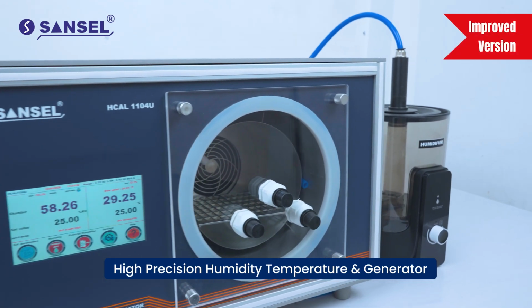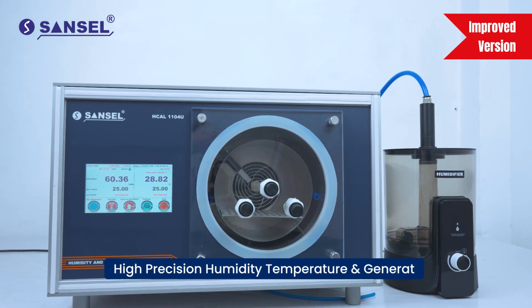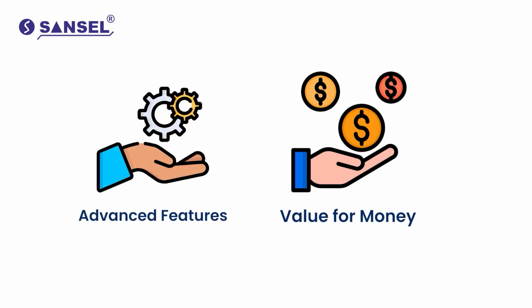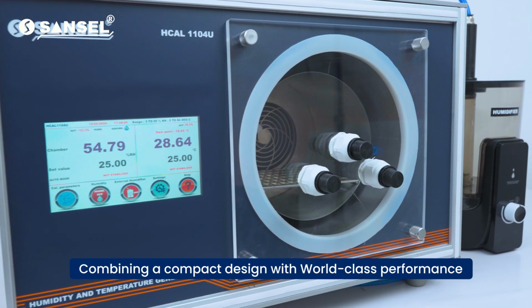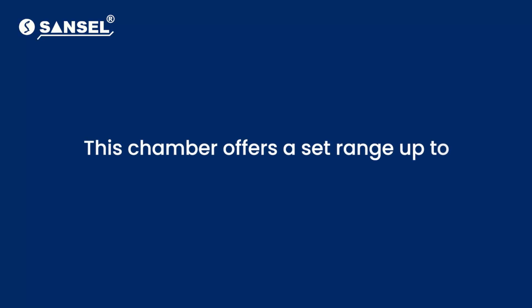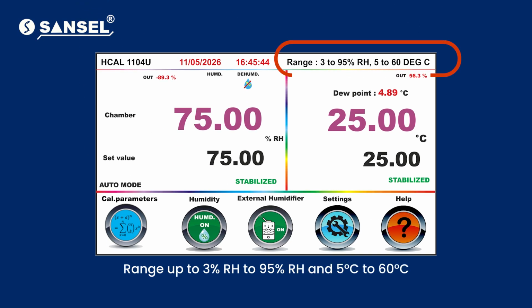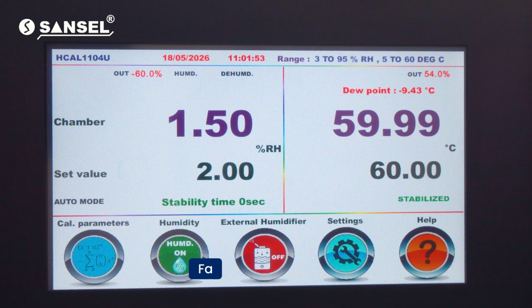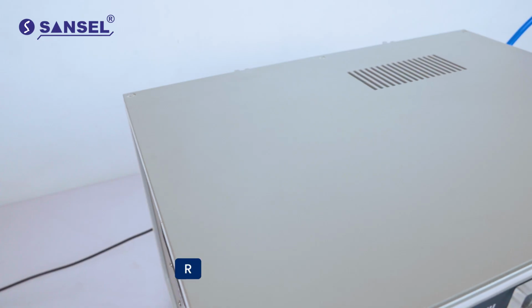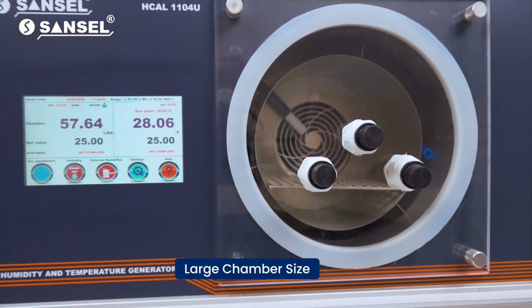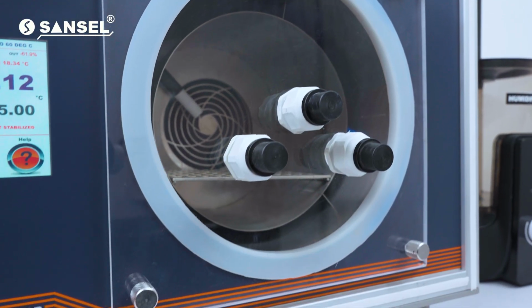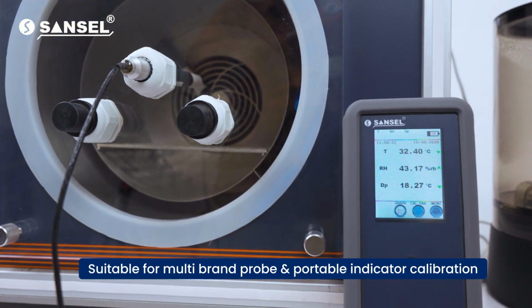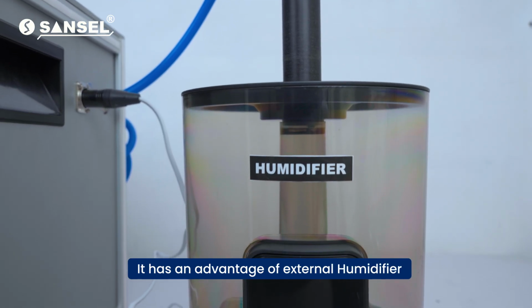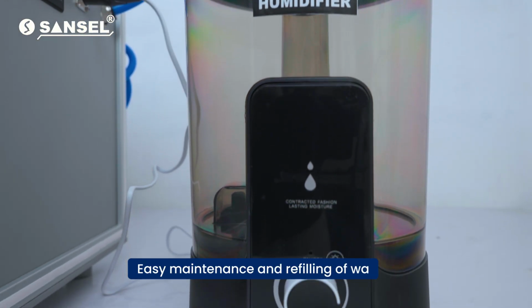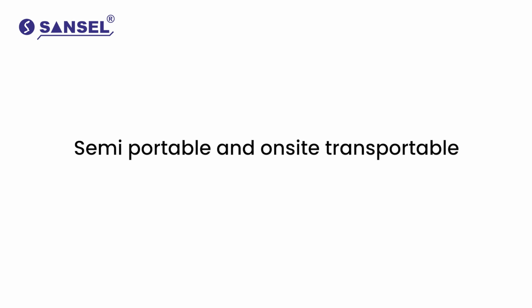Introducing the improved version of our high-precision humidity and temperature generator, packed with advanced features and value for money, combining a compact design with world-class performance. This chamber offers a set range of 3% to 95% relative humidity and 5 degrees Celsius to 60 degrees Celsius. It delivers fast and stable performance, with a rugged aluminum enclosure, a large chamber size, and a replaceable front door suitable for multi-brand probe and portable indicator calibration. It has the advantage of an external humidifier for easy maintenance and refilling of water, and is semi-portable and on-site transportable.